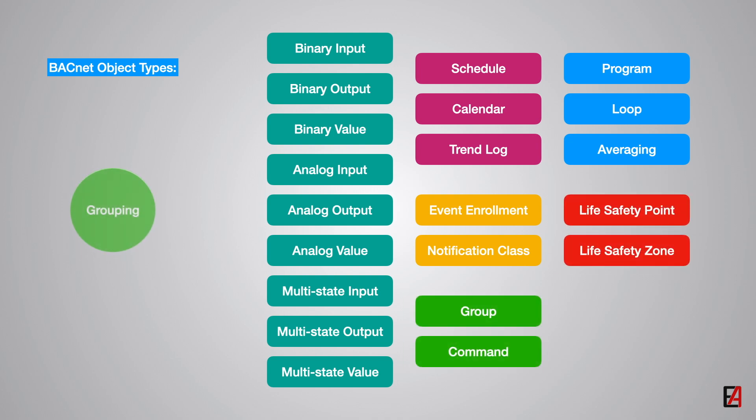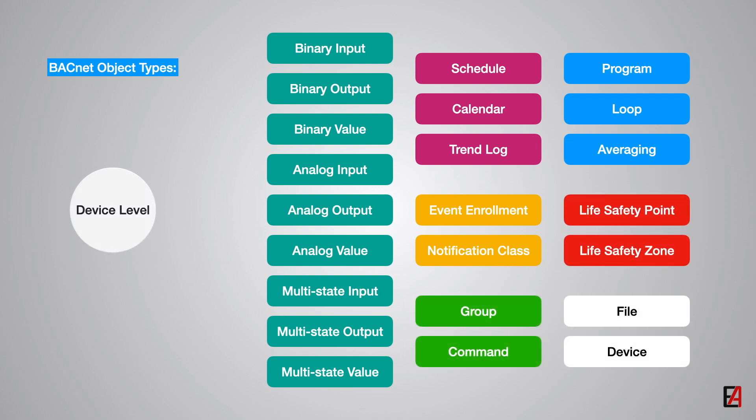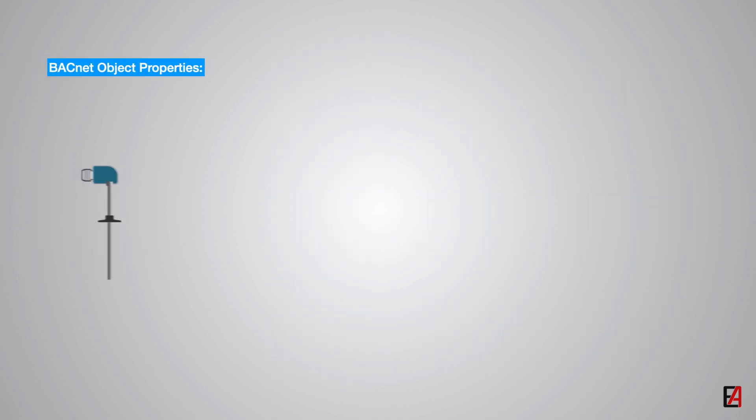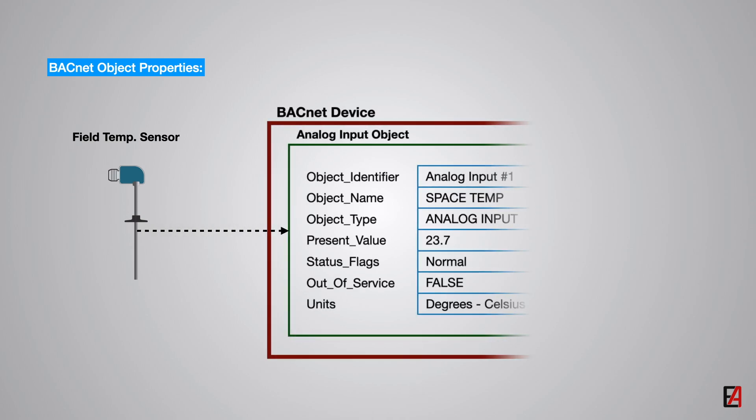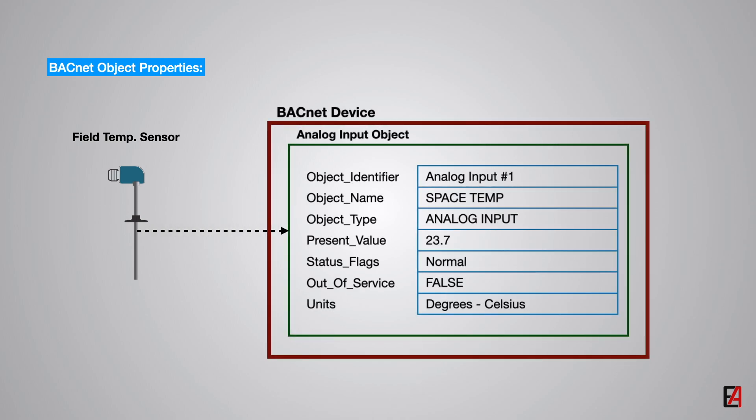Each object has a standard set of properties that defines the object and its current state. For example, each analog input is represented by a BACnet analog input object which has a set of properties like object identifier, object type, present value, description, units, etc. The BACnet standard identifies 123 different properties of objects. Some of the properties are required and some are optional.